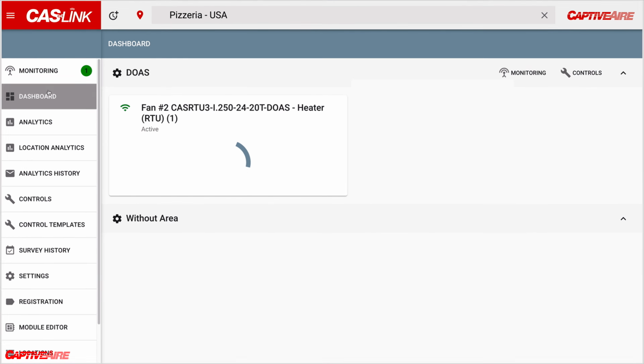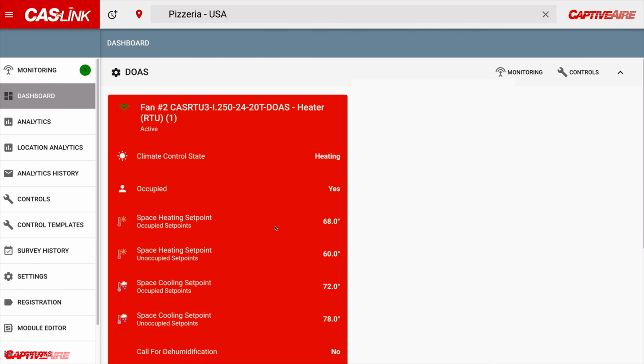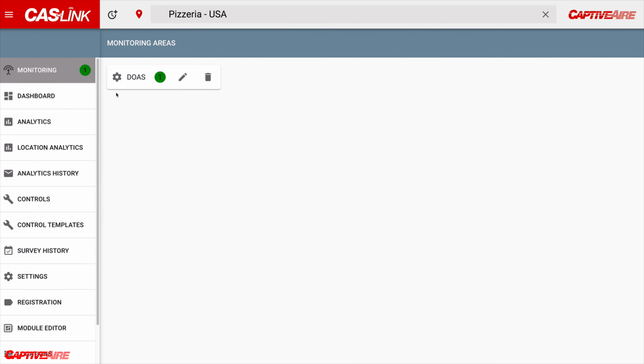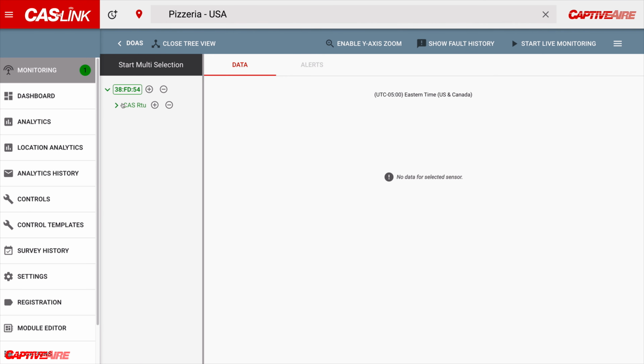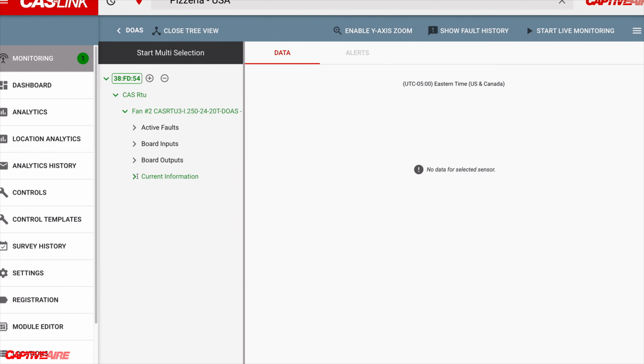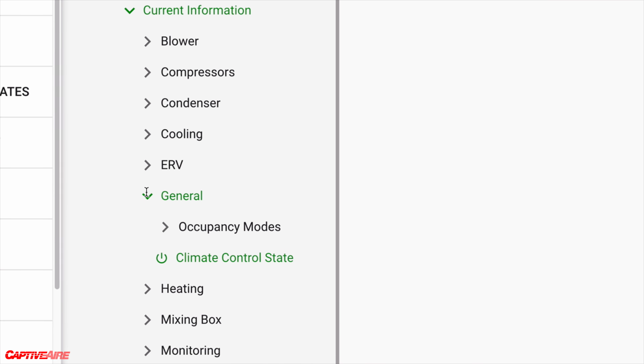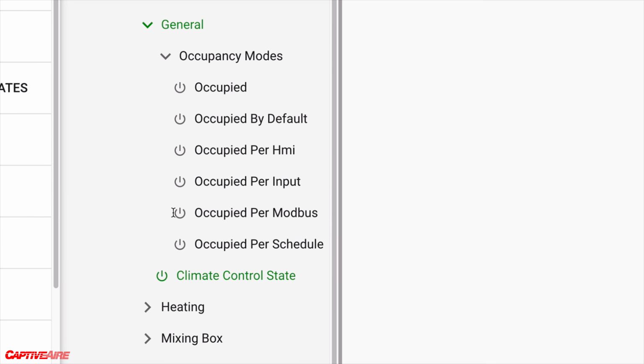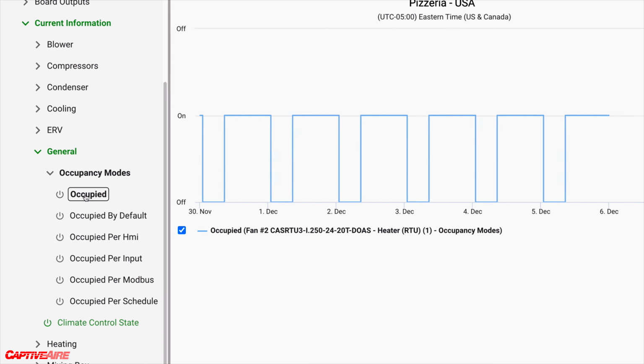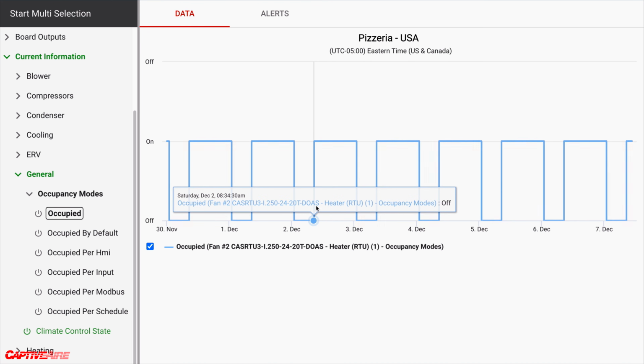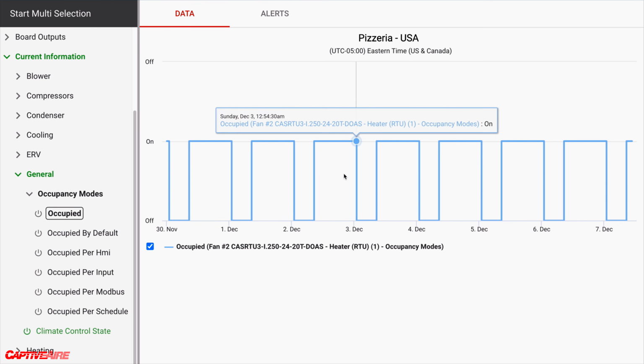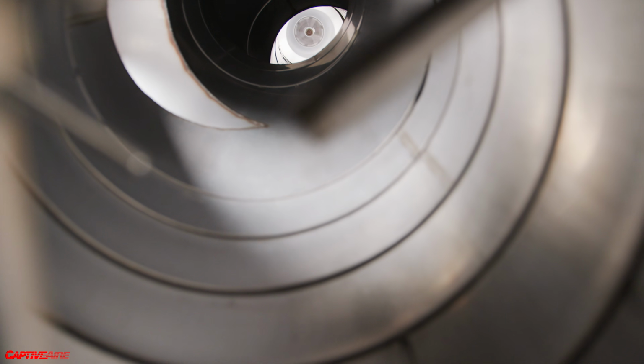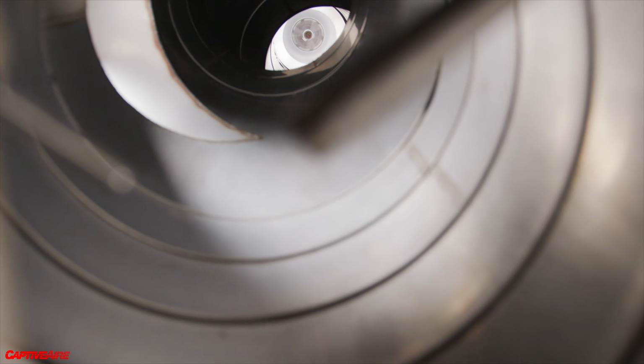So I've just pulled up, let's make sure this was the right site. In troubleshooting, they always say, check the easiest and most obvious thing first. So Chris will do exactly that. He'll check the occupancy modes and scheduling first to make sure that the unit isn't running at night when nobody's in the building. That is a quick and easy way to waste a lot of money if we find out that somebody's turning these hoods on or the schedule wasn't set up properly and these things are running 24/7 instead of only during these occupied times.